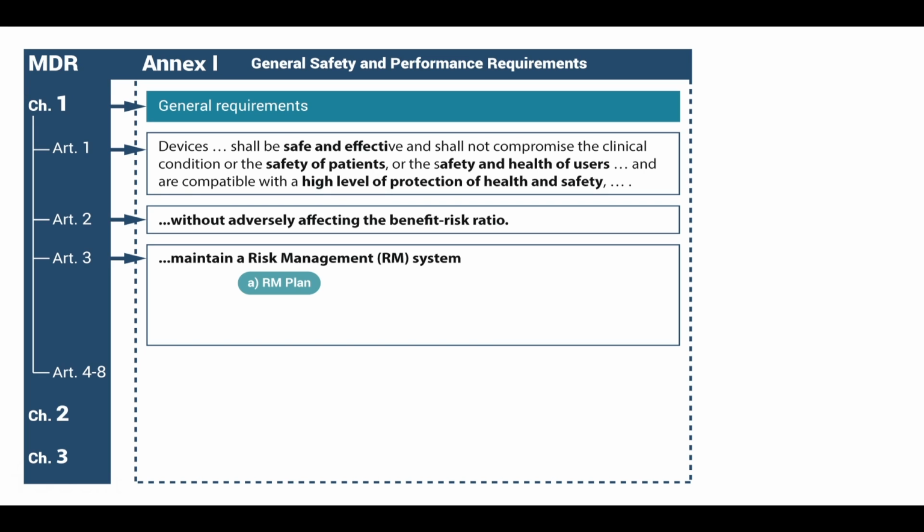Article 3 explains how your risk management system should be set up. First of all, you must make a risk management plan that describes your risk management system. Next, you should perform a full analysis to inventory all risks of your device throughout its entire life cycle and assess and estimate these risks.